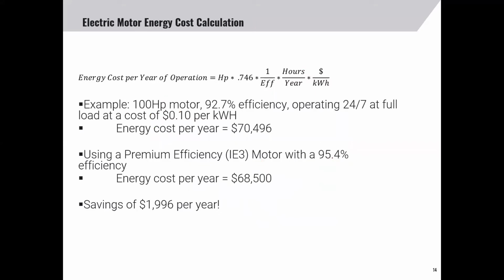So here's an example to put total cost of ownership in perspective. Let's take the example of purchasing a 100 horsepower motor. And as you can see there, the efficiency is 92.7%. This motor is operating 24 hours a day, 7 days a week, and it's fully loaded. Your cost per kilowatt hour is 10 cents. The energy cost per year is over $70,000.